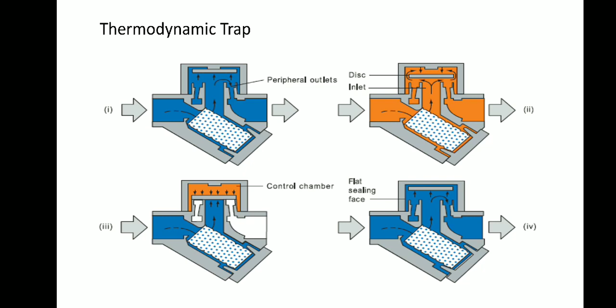Then figure 2: hot condensate flowing through the inlet passage into the chamber under the disc drops in pressure and releases flash steam at high velocity. This high velocity creates a low pressure area under the disc, drawing it towards its seat. In figure 3, at the same time, the flash steam pressure builds up inside the chamber above the disc, forcing it down against the incoming condensate until it seats on the inner and outer rings. At this point, the flash steam is trapped in the upper chamber and the pressure above the disc equals the pressure being applied to the underside of the disc from the inner ring. However, the top of the disc is subject to a greater force than the underside as it has a greater surface area. Eventually, the trapped pressure in the upper chamber falls as the flash steam condenses. The disc is raised by the now higher condensate pressure and the cycle repeats.